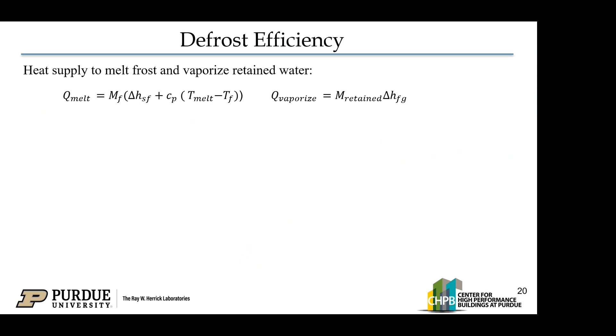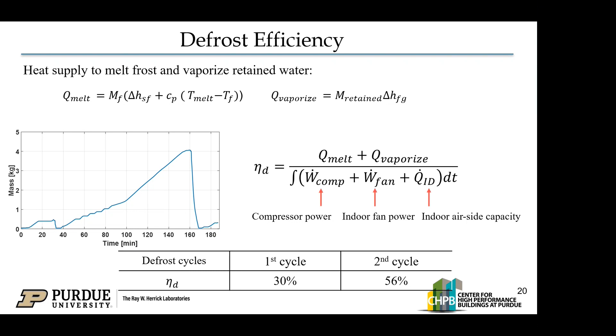And using the model, we can evaluate the defrost performance of this unit, that is, we can evaluate the defrost efficiency. So we need to predict the total amount of frost accumulation. Then the efficiency is defined as the heat that is supplied to melt all the frost and vaporize the retained water over all the energy input to the system. Here we also include the heat transfer from the indoor environment to penalize the defrost cycle, because you are taking heat from indoor, which could cause some problems. And for this test, the first defrost cycle has 30% efficiency. The second one has 56%, a higher efficiency, because significantly more frost accumulated for the second cycle.